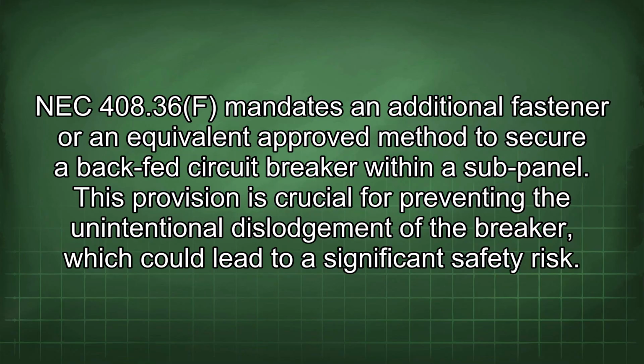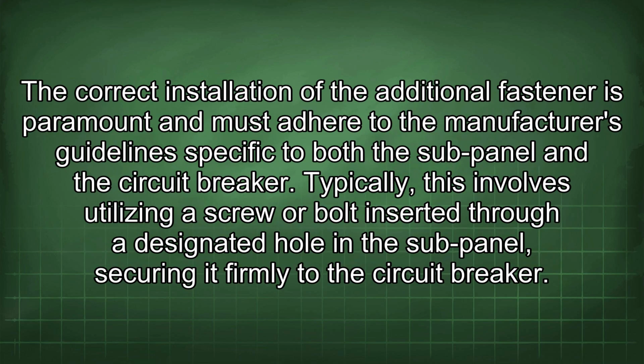NEC 408.36 mandates an additional fastener or an equivalent approved method to secure a backfed circuit breaker within a subpanel. This provision is crucial for preventing the unintentional dislodgement of the breaker, which could lead to a significant safety risk. The correct installation of the additional fastener is paramount and must adhere to the manufacturer's guidelines specific to both the subpanel and the circuit breaker.